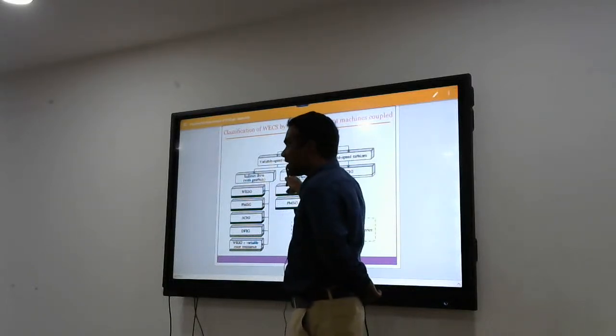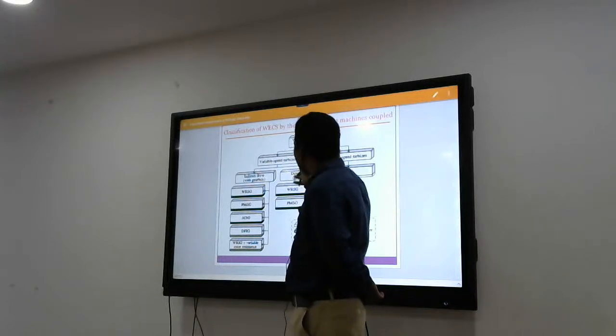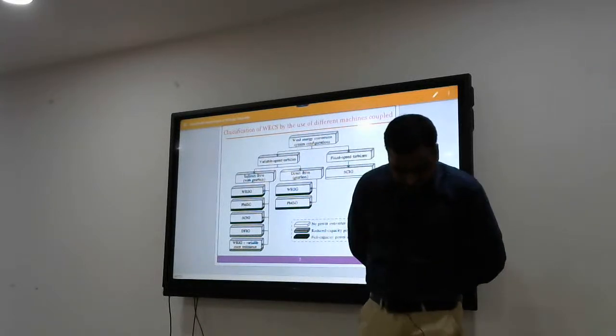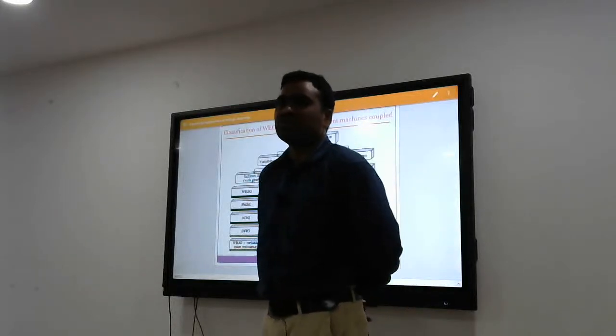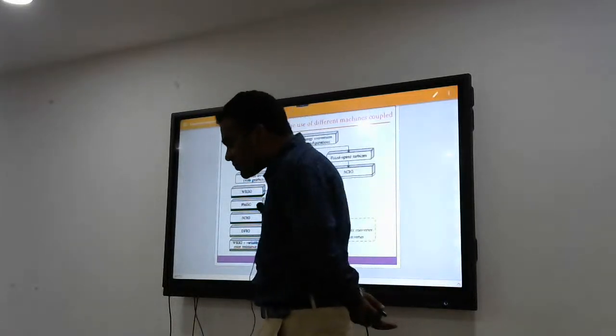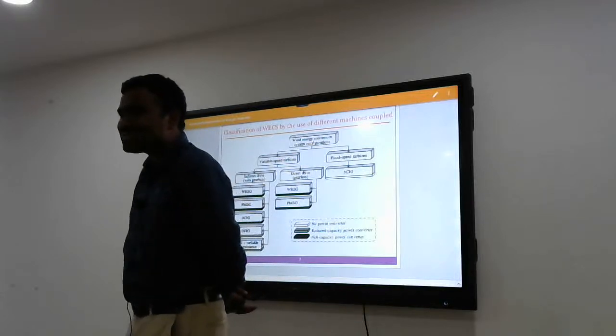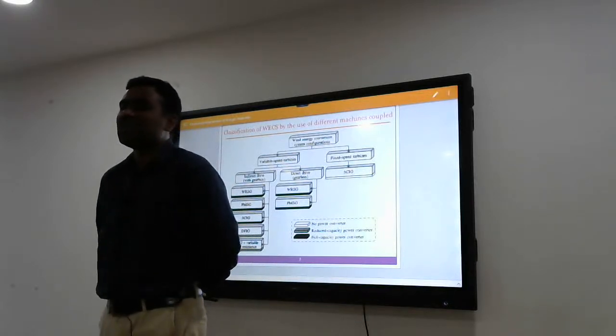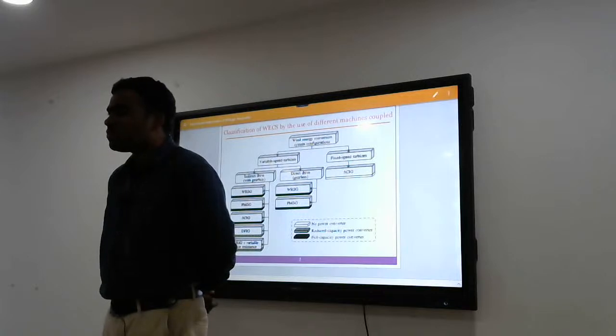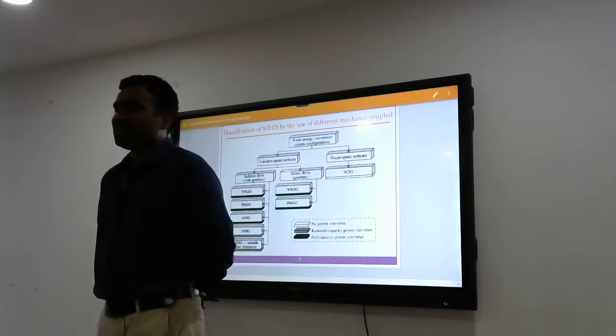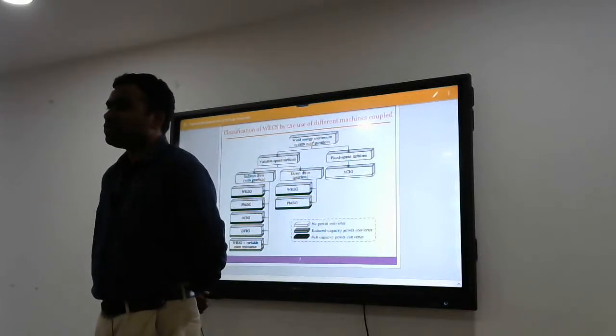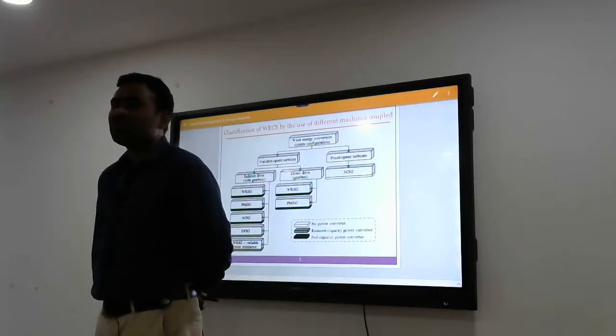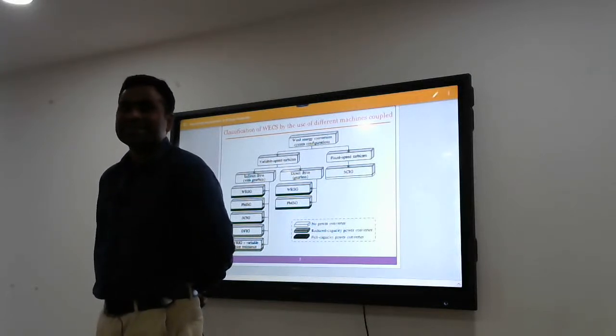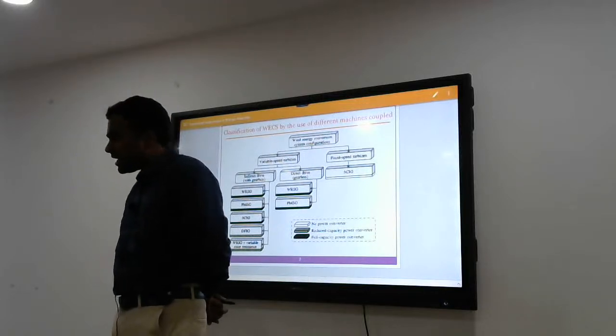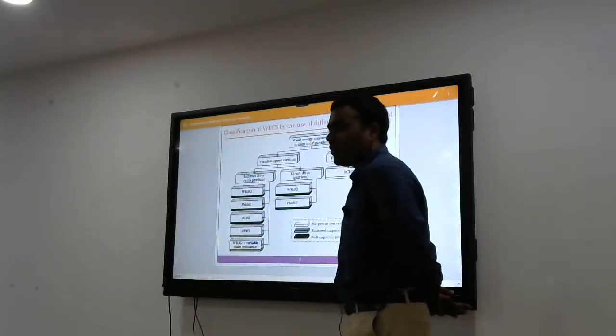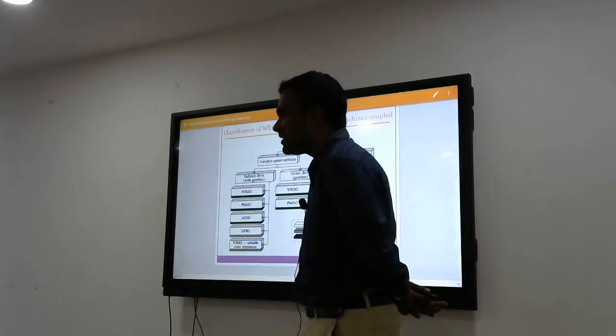In variable speed wind turbines, there are two types: one with gearbox and one without gearbox. There may be some cases where without gearbox is also possible. If you don't have a gearbox, the speed is less. If speed is less, to attain a certain frequency, you should increase the number of poles, because as your speed is less, to attain a certain frequency you have to increase the number of poles.